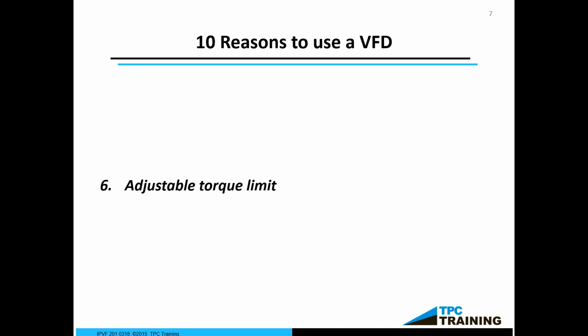Adjust the torque. We already said 3 foot-pounds of torque per horsepower. Maybe you're winding wire or taking tension on something. Based on that earlier discussion of the volts to hertz ratio, you would very easily be able to adjust the torque, and not only adjust it, but set limits also. You don't want to over torque something. So when you program a drive, you'll be able to adjust whatever torque limit you wish.